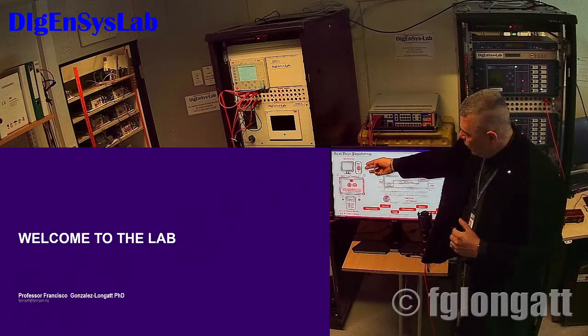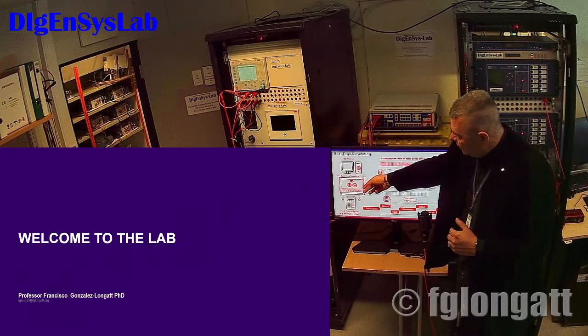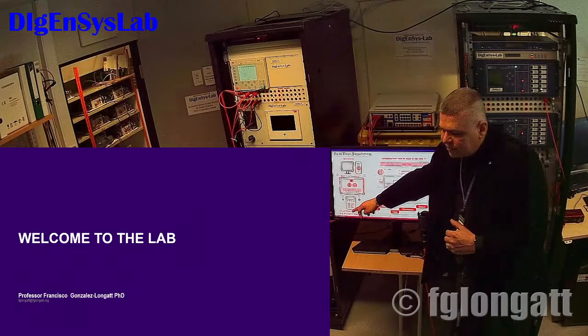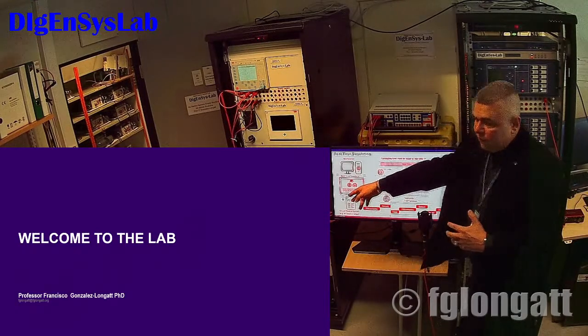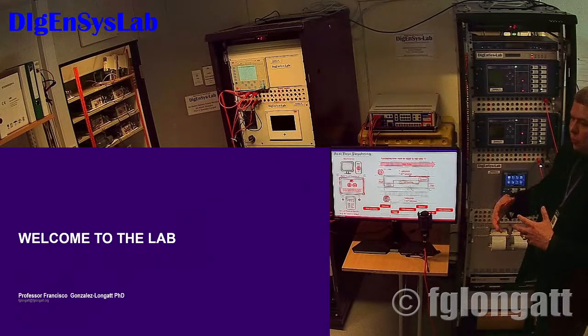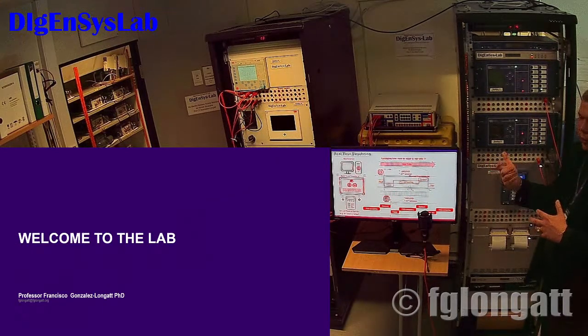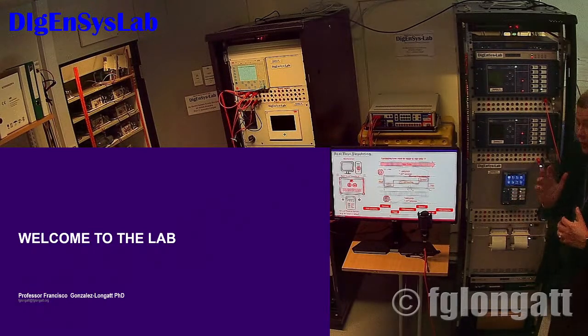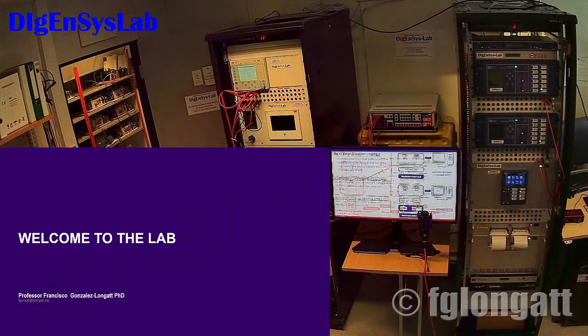Relay in the loop. We have the model. We put the model inside the simulator, and then we send signals to the relay. And if the relay opens, it will send the signal back and say, I open, okay? That is one way to test the relay. That is the best way to test the relay.